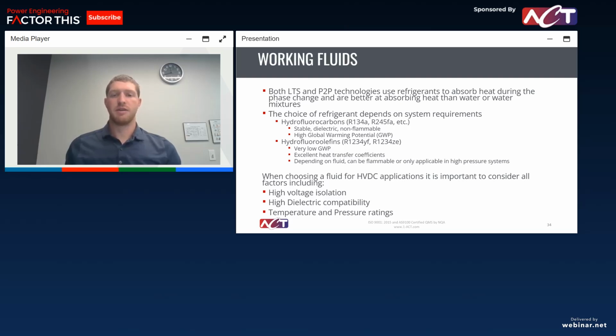So HFOs have been a newer thing. They've been specially designed to have lower global warming potential, but they still have excellent heat transfer coefficients. The one drawback is some of those HFOs are often mildly flammable, and some are only applicable in certain pressure ranges.